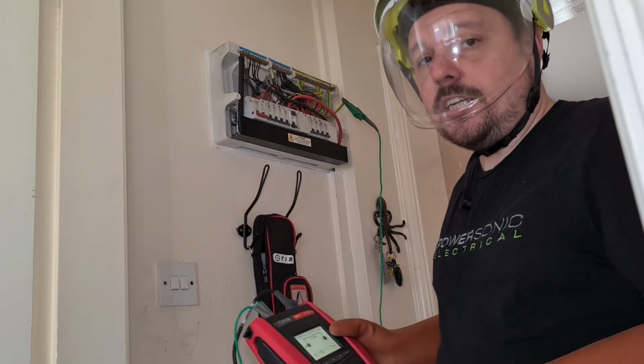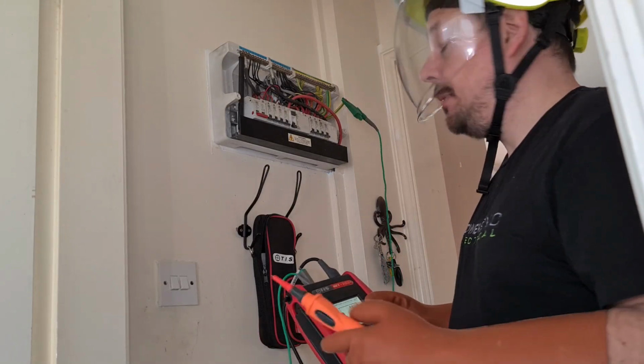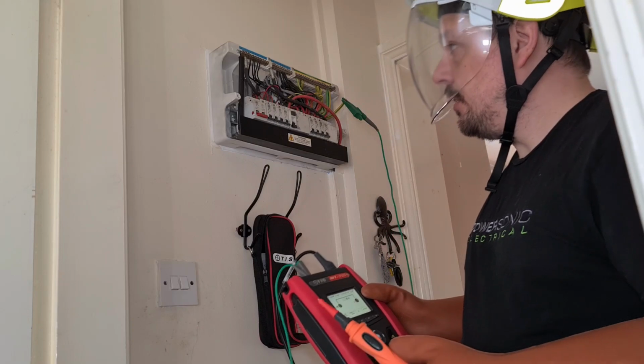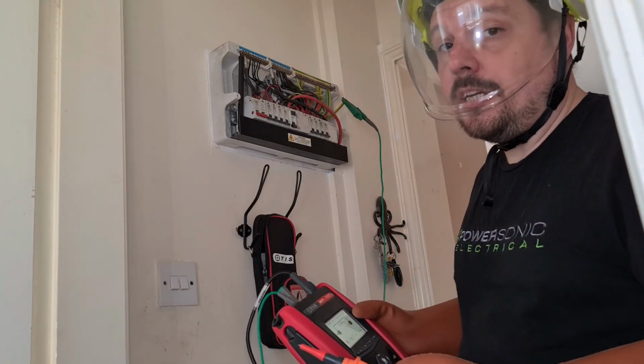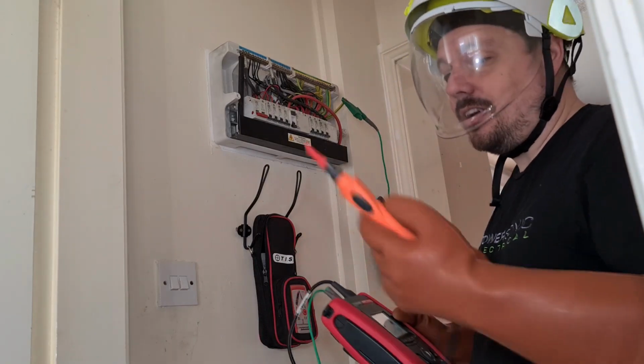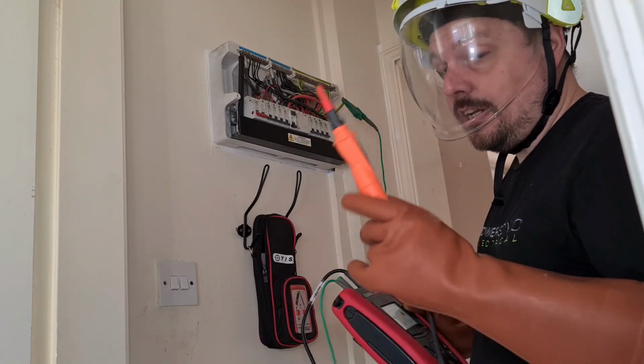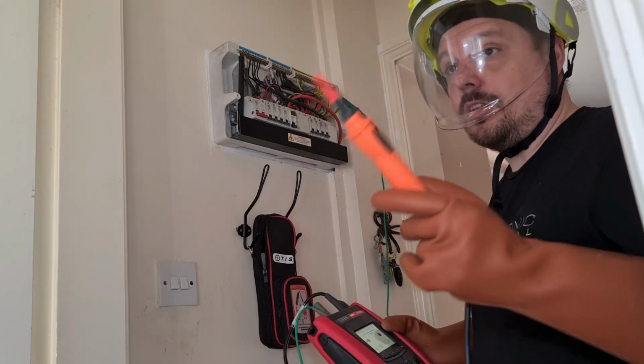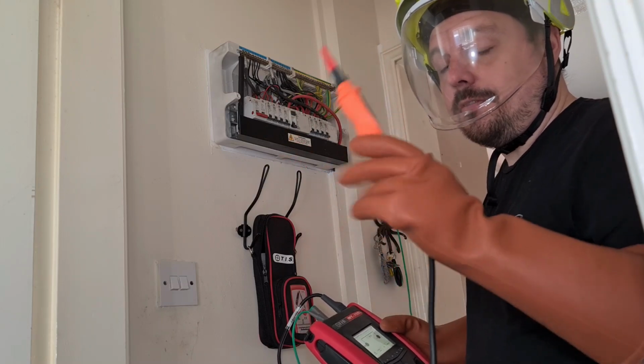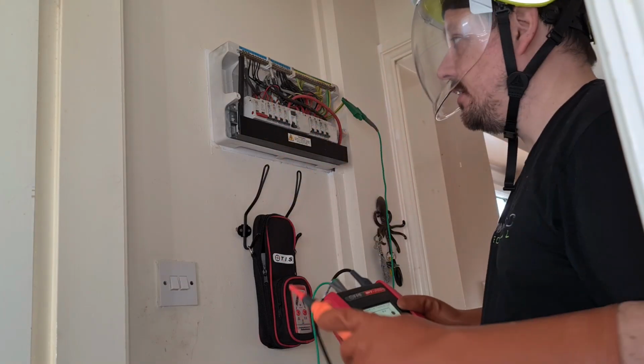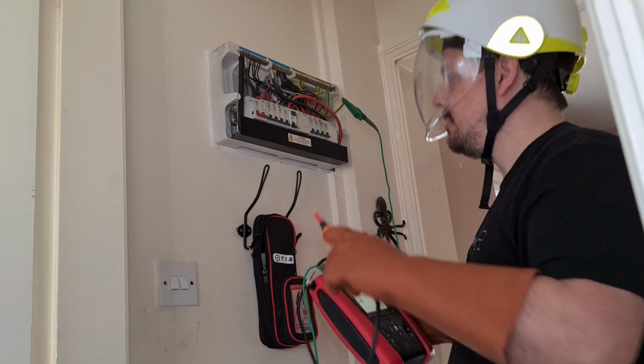This is the live test now for getting our Ze and our PFC. It's important, now we know this is energised, that you've got some PPE on - I've got the arc flash shield, my rubber gloves, and the GS38 probe on the end. I do have some long probe extenders, but I prefer this one because it's got a little button so I can start the test.